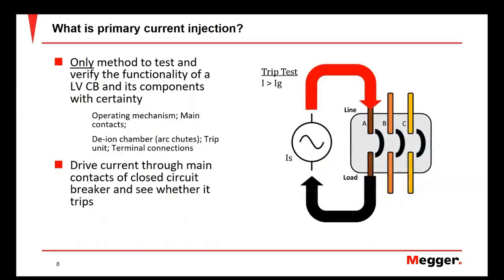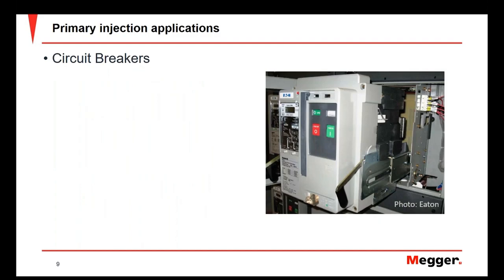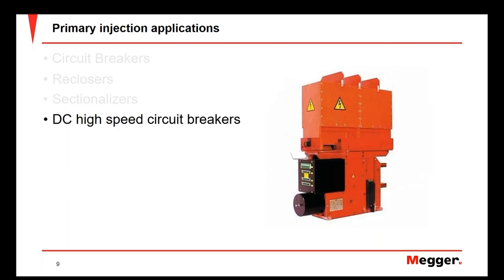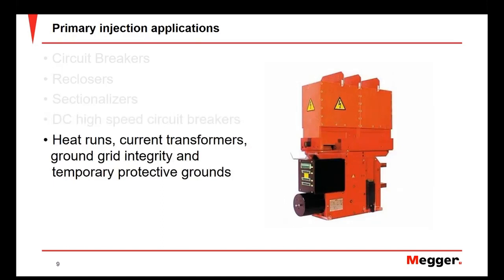Whenever we do this type of test, we drive current through a closed circuit breaker through the main contacts and verify that the overcurrent function is going to react as intended, or trip, whenever we push current through the breaker. Primary injection also applies to reclosers and sectionalizers that have overcurrent functions, DC high-speed circuit breakers, and can also be used to do heat runs, test current transformers, verify the integrity of ground grids, and test personal protective grounds.